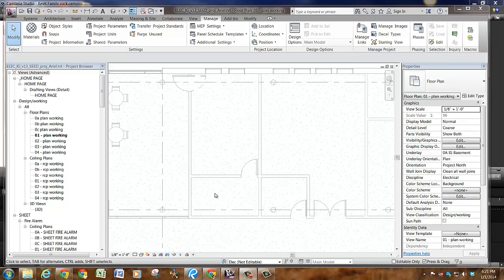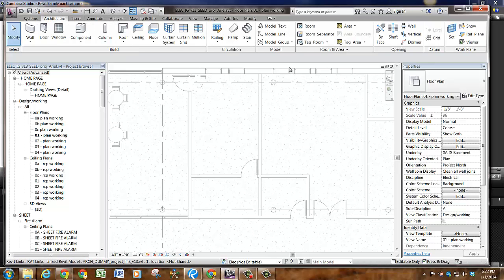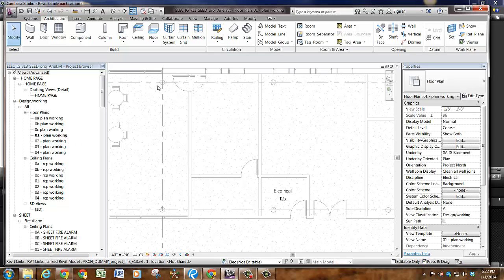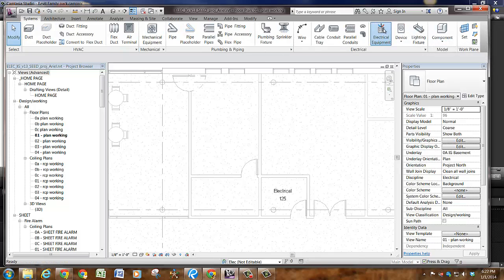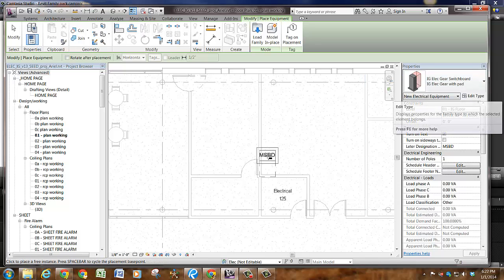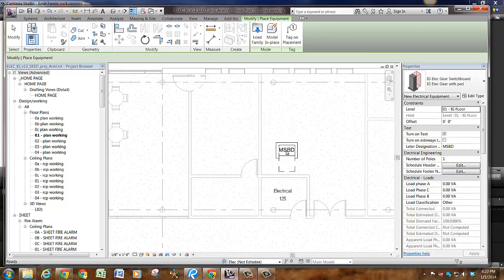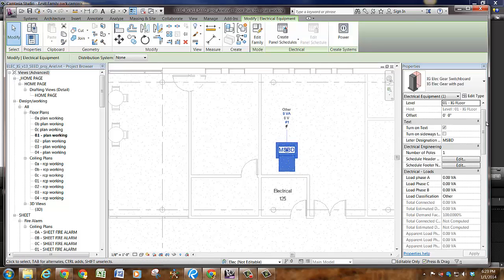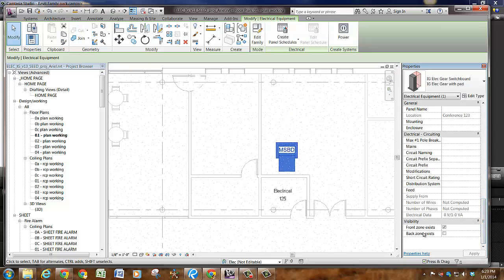When you're working in a background and you find your electrical room and want to fill it out with these different families, we'll show a bit about how families work in addition to naming conventions. Go to the architecture tab and select tag room to find your electrical room. I'm in a working view, which is what I want when first setting it up, and then we'll check out the sheet view and add any needed tags. Go to the systems tab and place an electrical equipment. When you first place the switchboard, you'll need to edit type to make it the shape and size you want. Top zone height is how tall the access zone above is. Front zone depth is how deep the front access zone is. If you want a back zone, scroll down and click 'back zone exists' to set its depth.